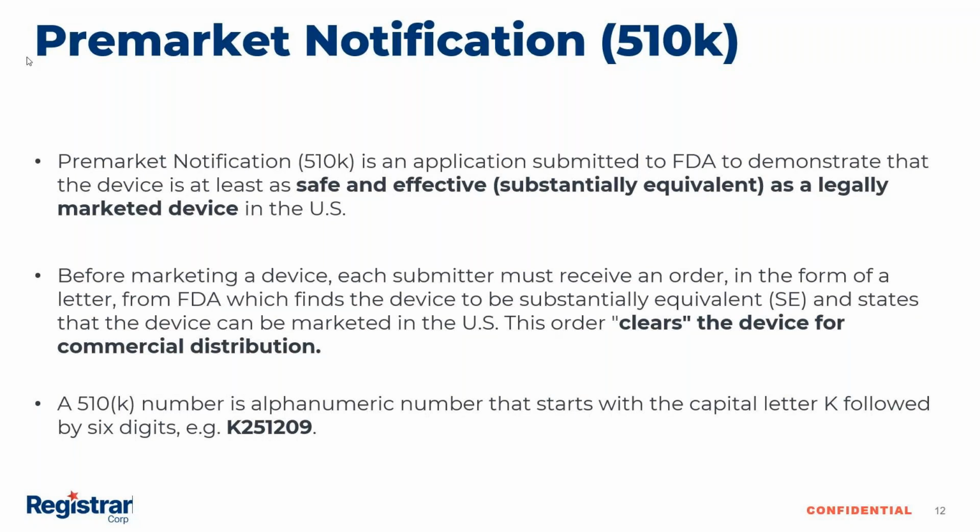A 510K number is an alphanumeric number that starts with a capital letter K followed by 6 digits. So, for example, K251209. That's the typical 510K number.